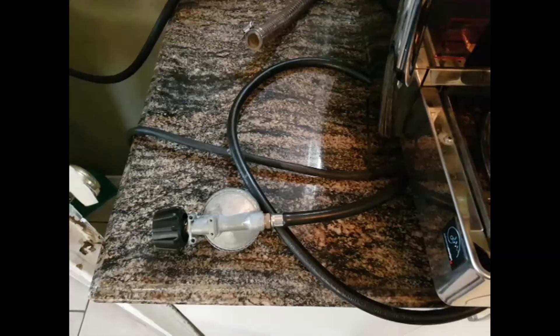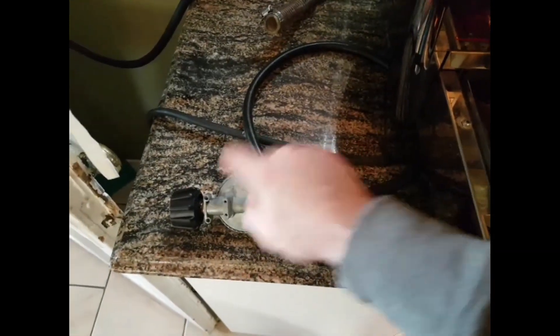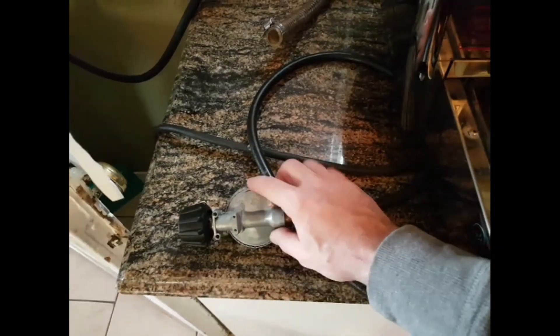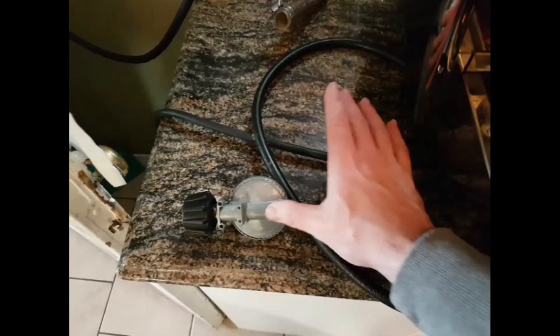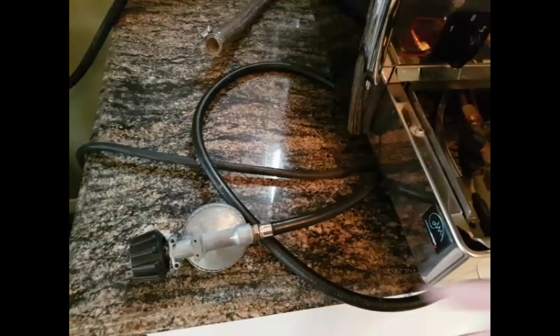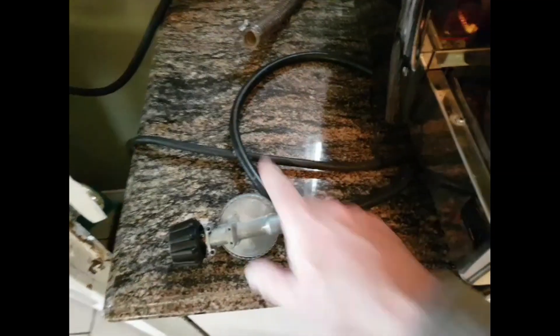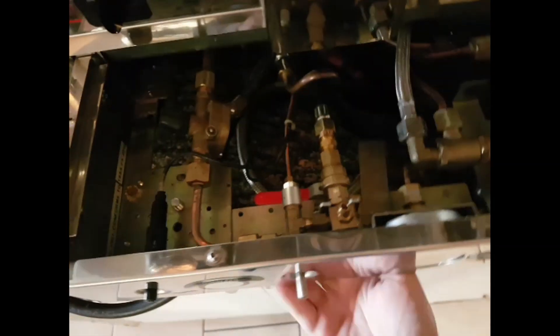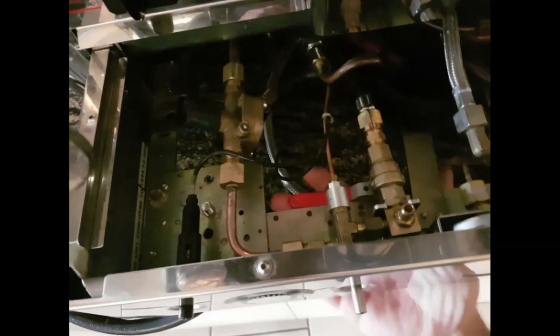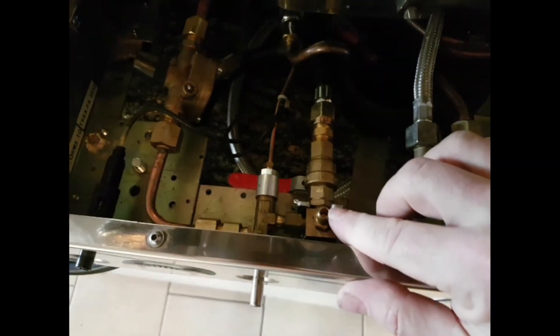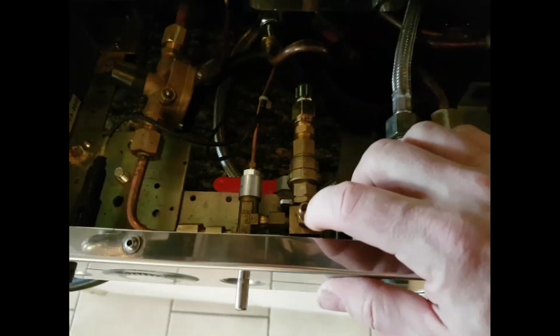Gas burners definitely my favorite part of these machines. So quick fuel flow walkthrough here. From your cylinder, you have your LP gas regulator. I call them vaporizer just because we've got two regulators on here and it eliminates confusion. And here's your fuel hose. It enters right here. There is a ball valve that's used as a shutoff right here. So here it's open, here it's closed. Here is your pressure tap for checking the regulated pressure from your vaporizer.